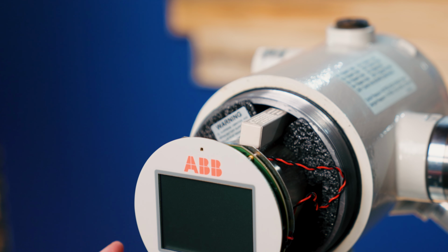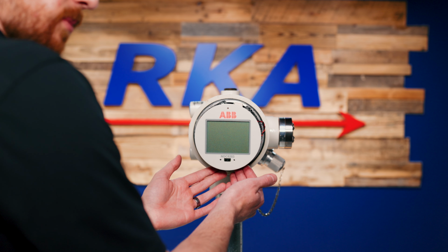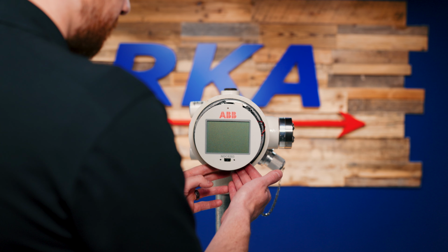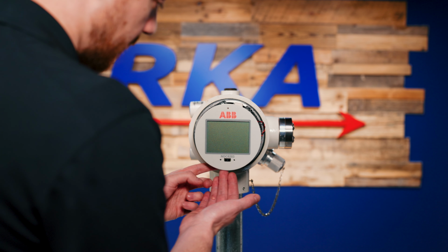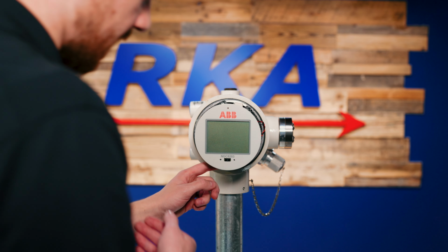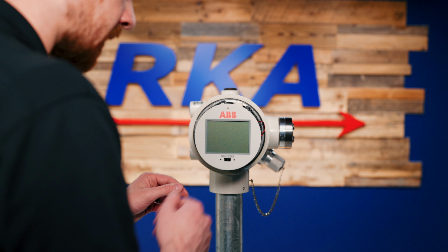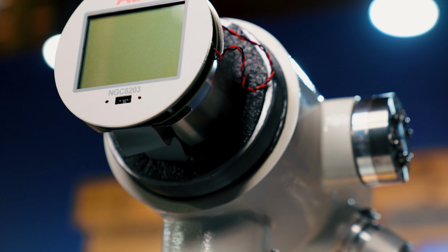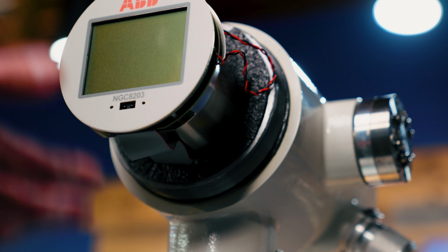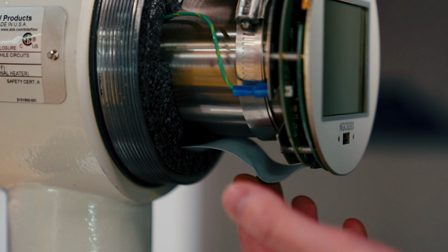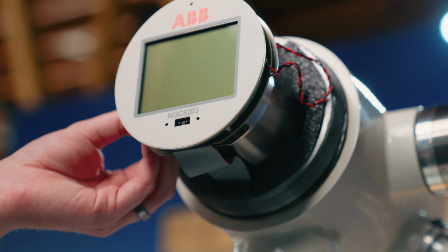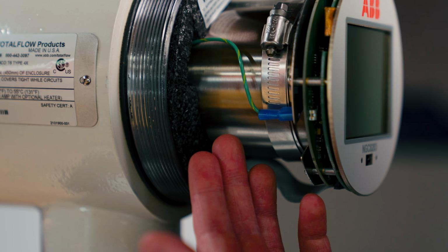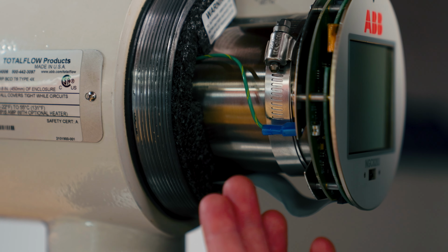The other thing to watch is the ribbon cable down below. We want to keep it from getting damaged, as it is very delicate—pulling on it or pinching it can damage it, and you'll have to replace it, which is not fun. So be very careful and aware of the ribbon cable. Also, on the other side of the display, there is a grounding cable connected to it.